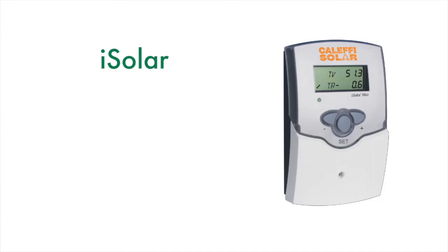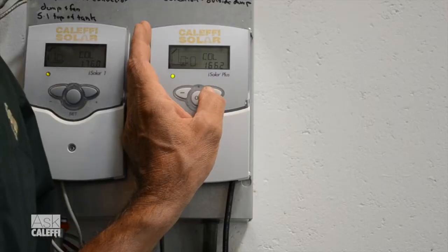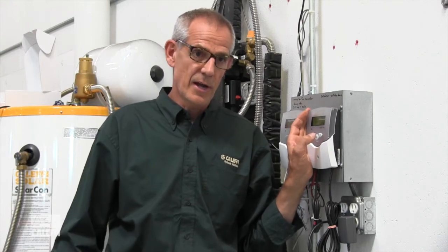I want to talk about a commonly used function on the Isolar Plus control called Arrangement 3, which is for a backup heating source. If you have a solar tank and you want to also fire it with a boiler on an upper coil, now if you happen to have an iSolar 1 control, it's called Arrangement 2 in there — sorry about that. Arrangement 3 is essentially a thermostat function: it turns on the heat source until it reaches a certain temperature, then turns off.